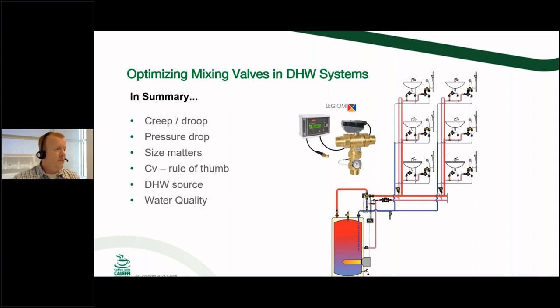Yeah, and if you've got crossovers anywhere else in the system too, if you've got that big pressure differential from one side to the other, say any single handle faucet cartridges that have failed, or maybe you've got a point of use mixing valve, again with check valves that have failed or have debris in them or anything like that, that's going to allow migration from one side to the other and cause issues there as well.